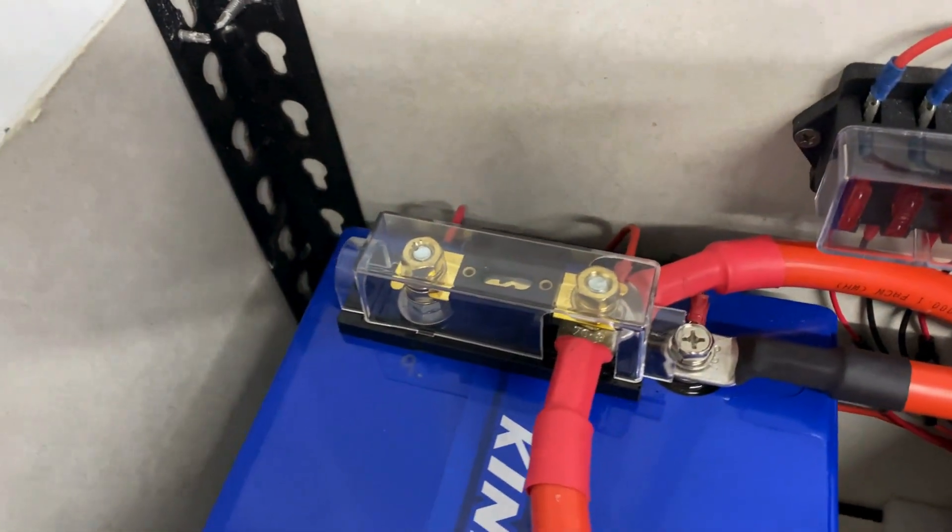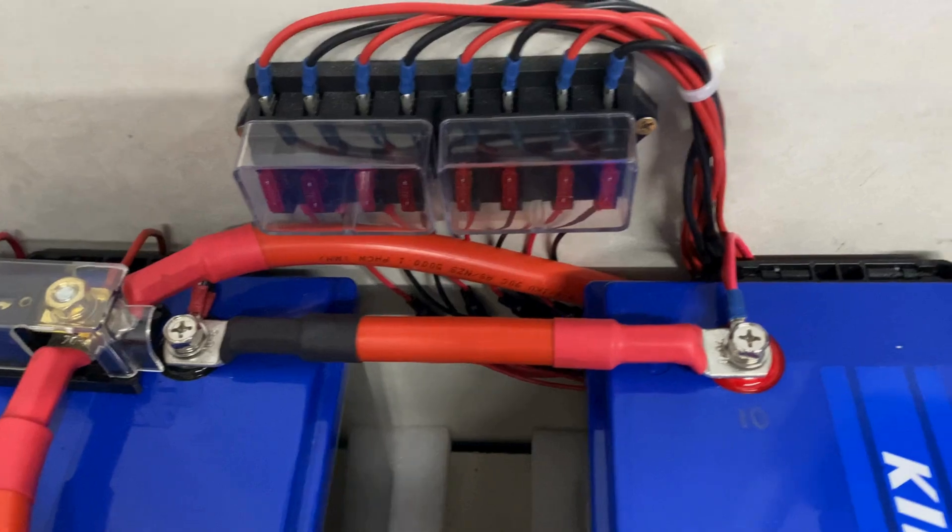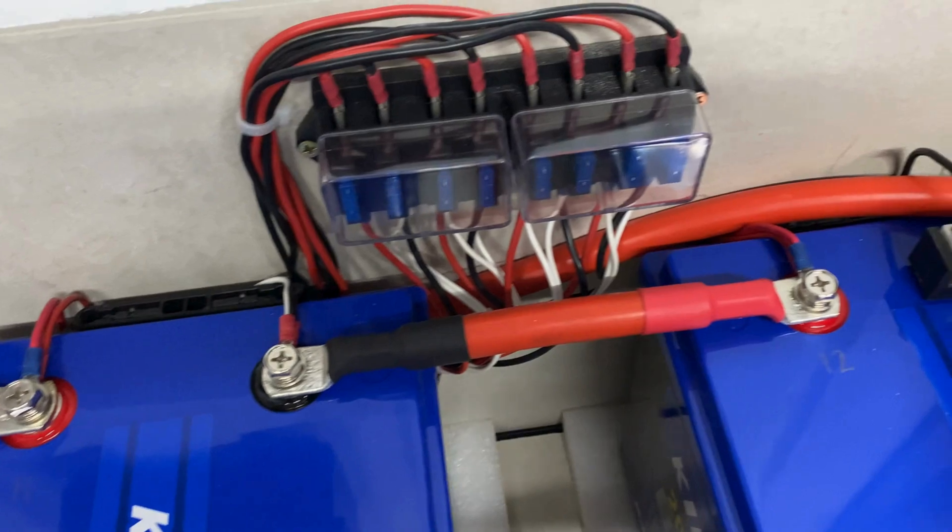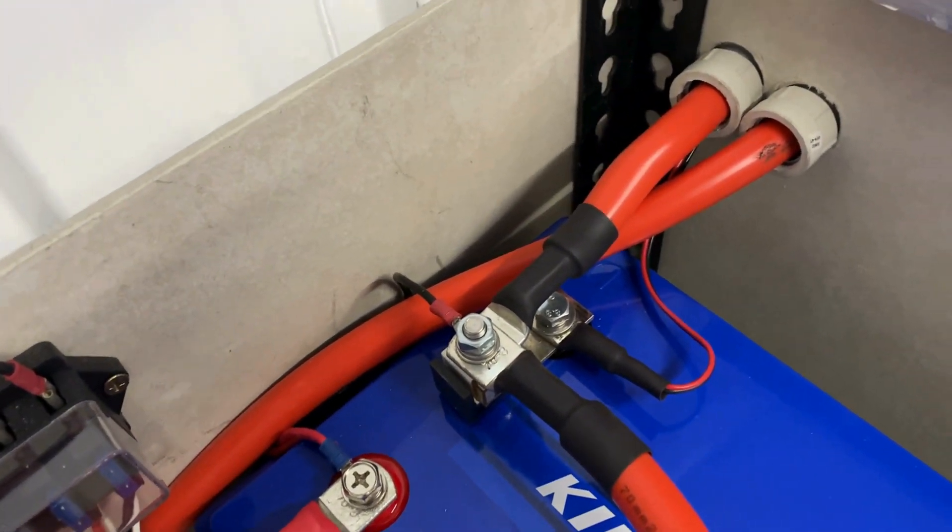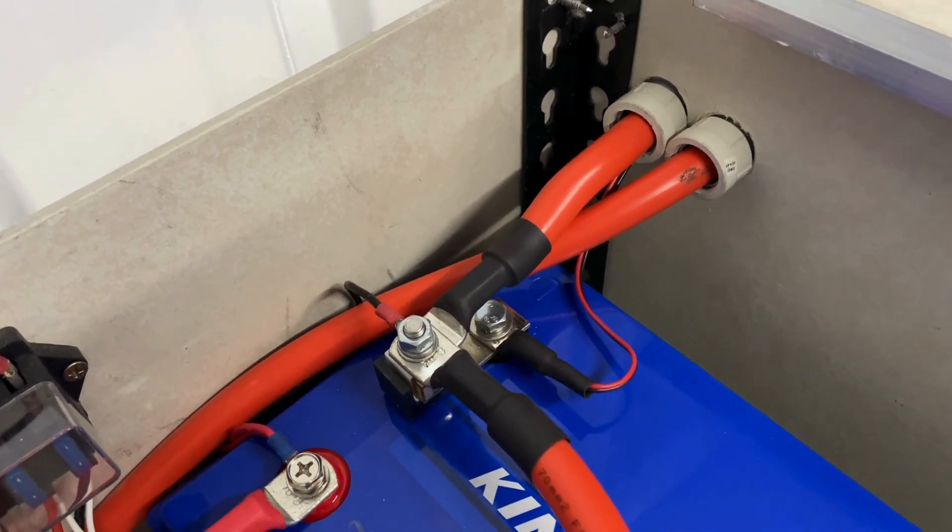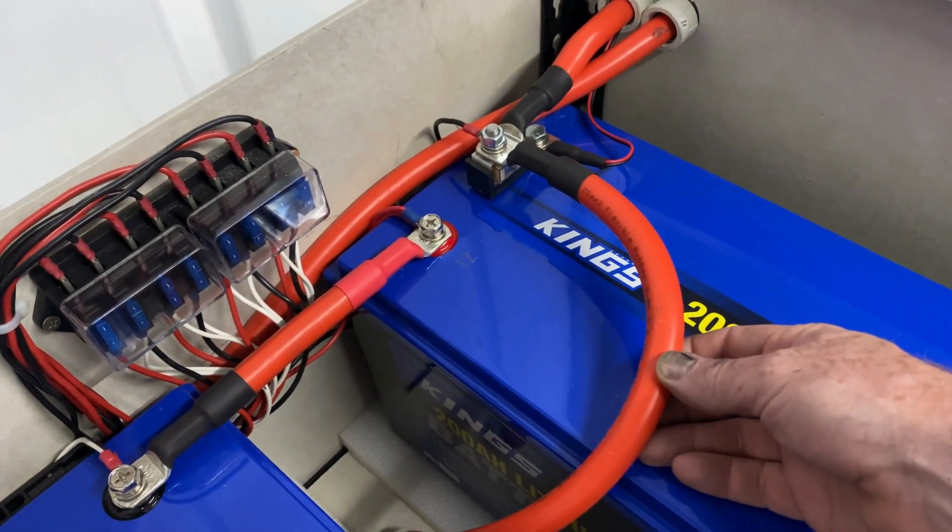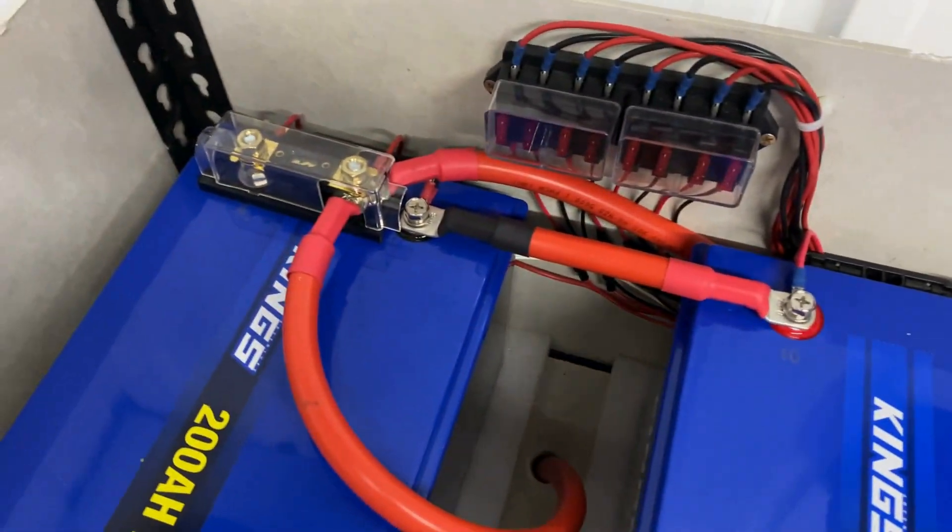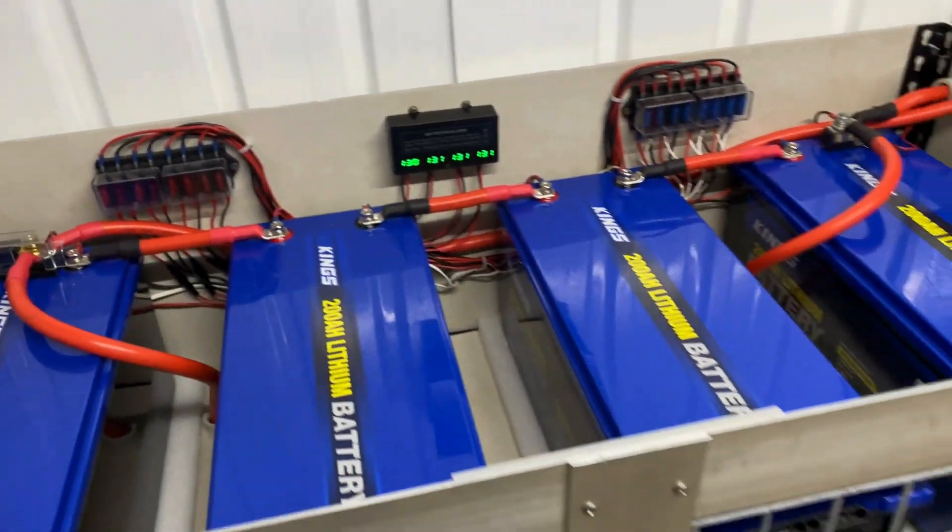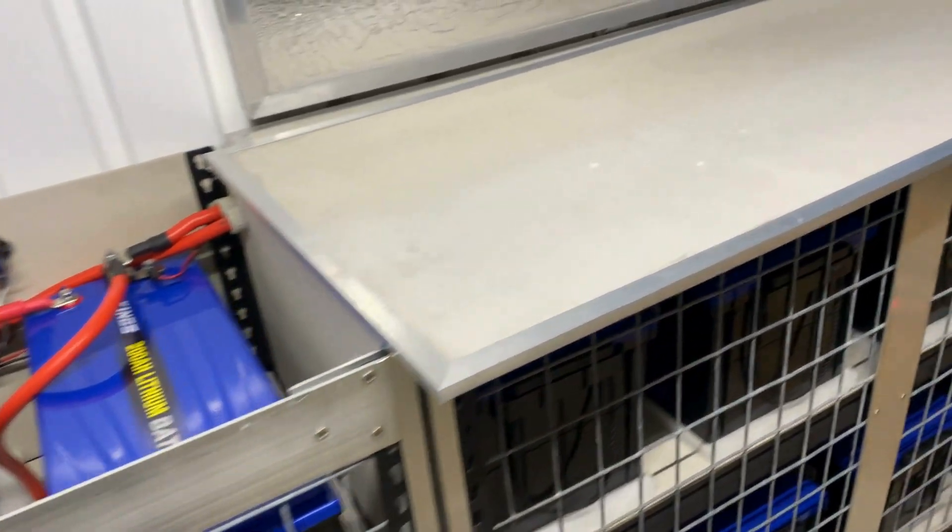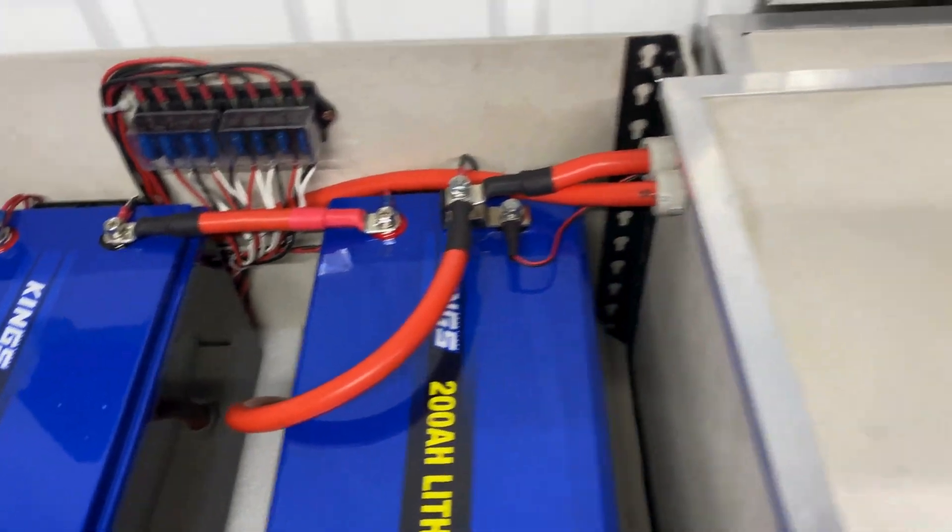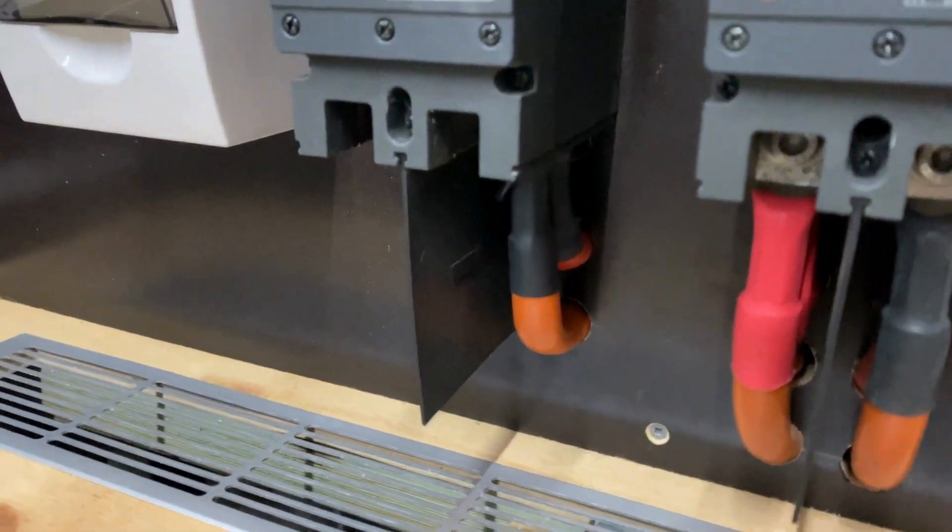So I've got a terminal post fuse up on the positive. Now series connection running between the batteries. Then off the end, another fuse, and this is where the parallel connection is made. This cable here runs straight down to the bottom bank, and so does this one. And then down the bottom, another set of cables runs back through, links up with this set. That set of cables runs through, links up with this set. There's another parallel connection like this, either end of that bank. And then those wires come through and feed onto the bottom of the MCCB.